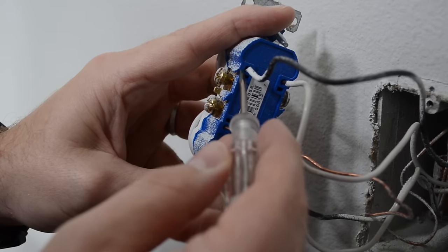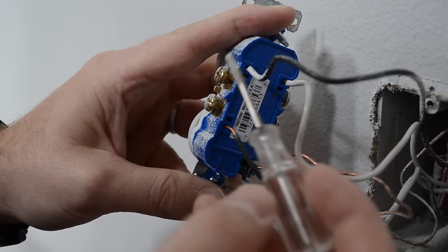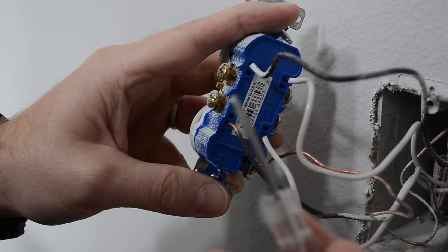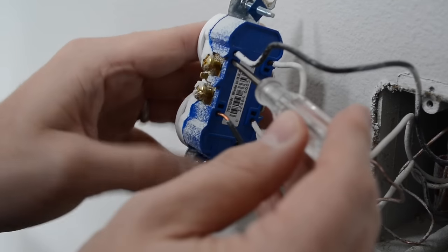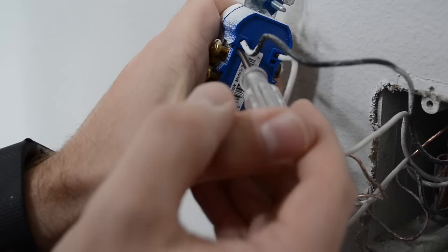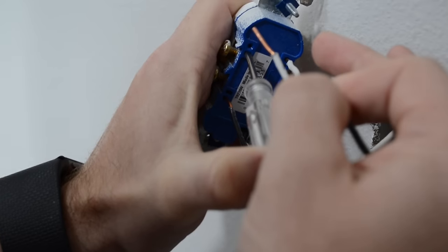There are two slots: one where the wire goes in and just under it there is a rectangular slot where you can take a small flathead screwdriver and push that in there. I use my thumb to push that in and at the same time I grab the wire with my other hand and it comes right out.